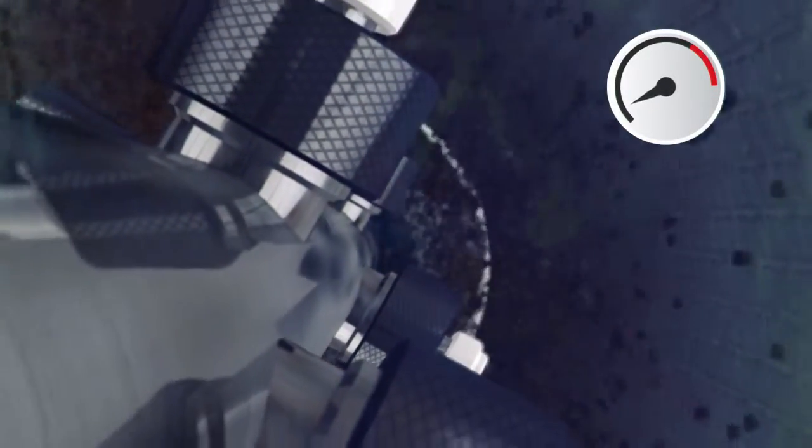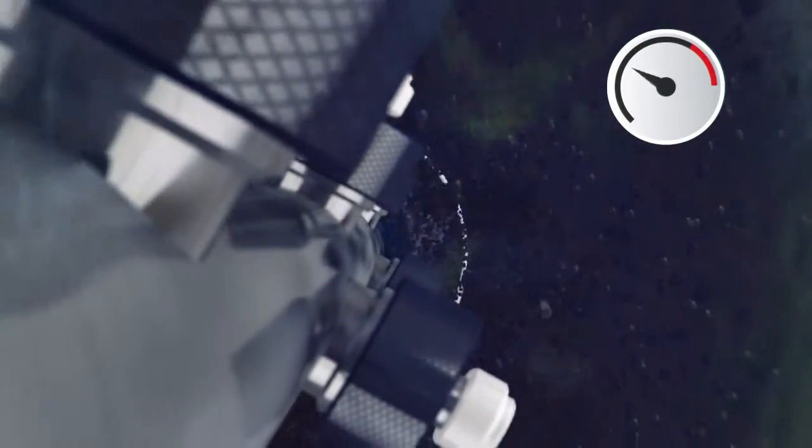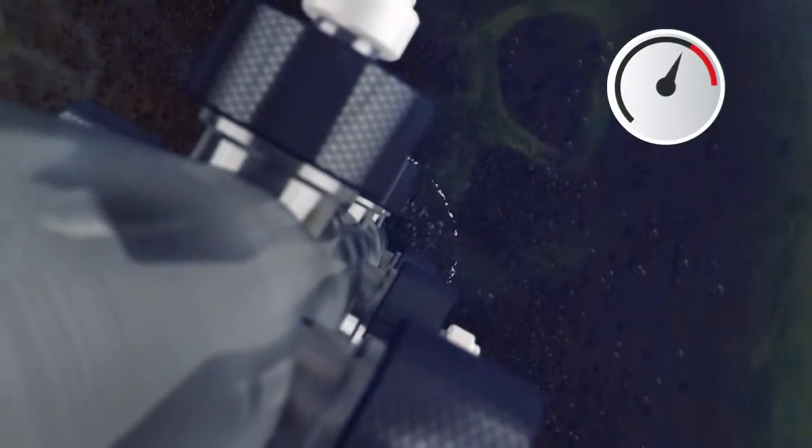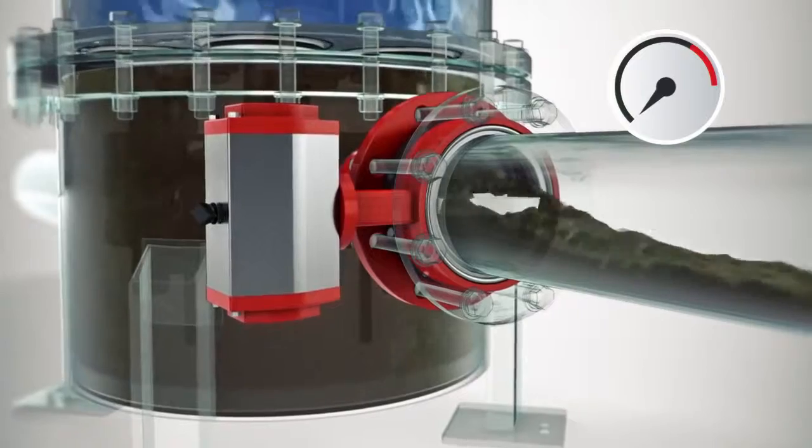suspended solid particles are trapped and accumulate on each screen's inner surface. Once the differential pressure reaches a preset level, the system activates its self-cleaning cycle by opening the flushing valve and starting the motor.